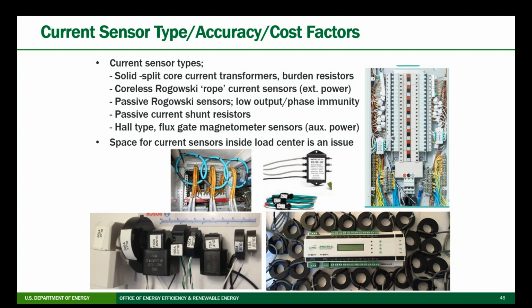If you've got 30 branch circuits, you've got 30 sensors that you have to cram into a space that's already full of wires. This one uses a concentrator hub where every 6 or 8 sensors go into a hub, and then the wire comes out of the hub. But then you have to have hubs. So you can see it's a spaghetti mess no matter how you look at it.